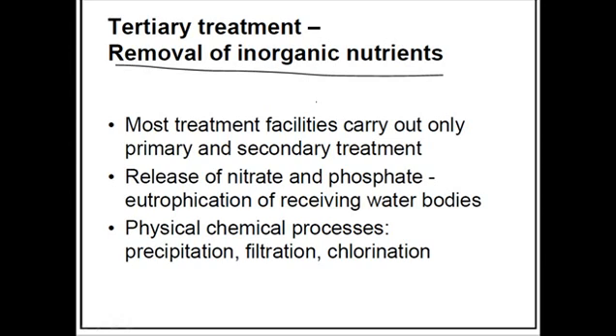In tertiary treatment for removal of inorganic particles, we do not use microorganisms — we use chemicals. Normally we use ferric chloride, and ferric chloride helps the different ionic particles to coagulate with each other and then finally settle down. Most treatment facilities carry out primary and secondary treatment.